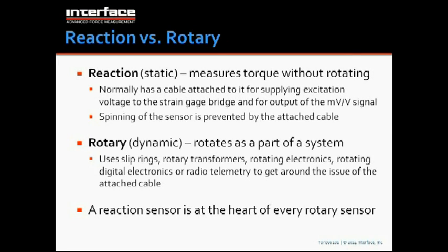And so a reaction sensor has a cable, and that cable or connector is attached to your instrumentation, and if you were to spin that sensor, the cable gets wrapped up and causes problems. So a reaction sensor could rotate. The only thing that prevents it from rotating is the cable.